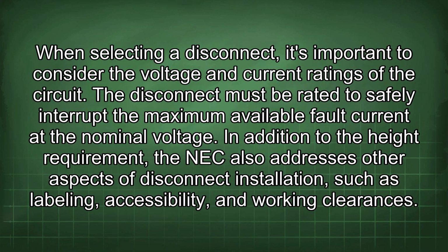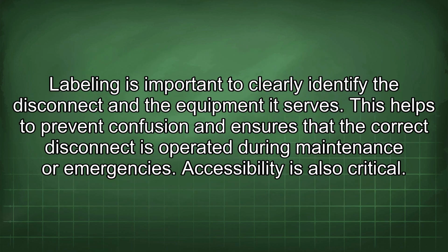When selecting a disconnect, it's important to consider the voltage and current ratings of the circuit. The disconnect must be rated to safely interrupt the maximum available fault current at the nominal voltage. In addition to the height requirement, the NEC also addresses other aspects of disconnect installation such as labeling, accessibility, and working clearances. Labeling is important to clearly identify the disconnect and the equipment it serves. This helps to prevent confusion and ensures that the correct disconnect is operated during maintenance or emergencies.